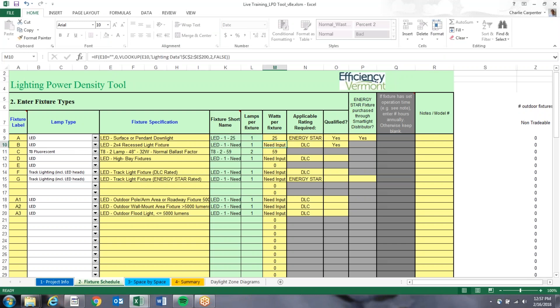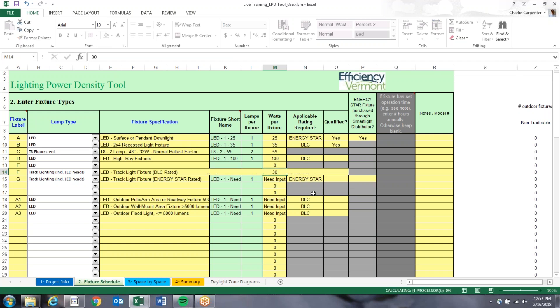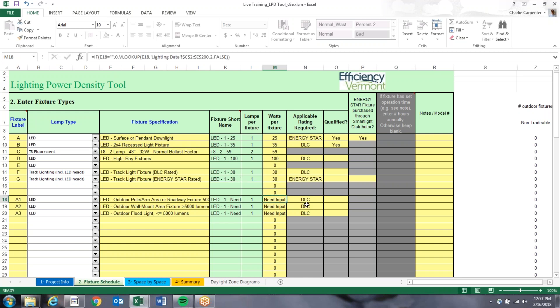I'll input some of the wattages: 25 watts for A, 35 watts for B. The fluorescent fixtures calculate themselves because the tool knows what wattage the lamps are and the ballast factor. For all the LEDs, you have to input the wattage — D is a 100-watt high bay, F is a 30-watt track head, G is also a 30-watt track head. For exterior fixtures: 75-watt pole, 35-watt wall mount, and 25-watt floodlight.